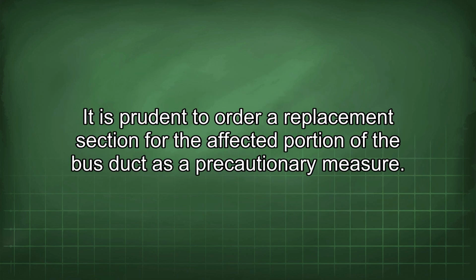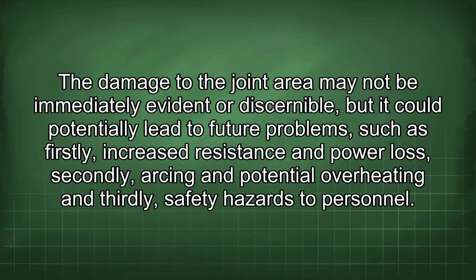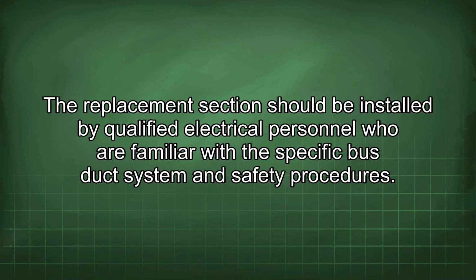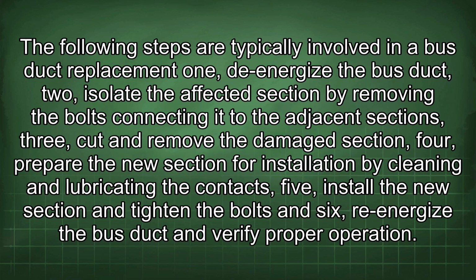It is prudent to order a replacement section for the affected portion of the bus duct as a precautionary measure. The damage to the joint area may not be immediately evident or discernible, but it could potentially lead to future problems, such as firstly, increased resistance and power loss, secondly, arcing and potential overheating, and thirdly, safety hazards to personnel. The replacement section should be installed by qualified electrical personnel who are familiar with the specific bus duct system and safety procedures. The following steps are typically involved in a bus duct replacement.